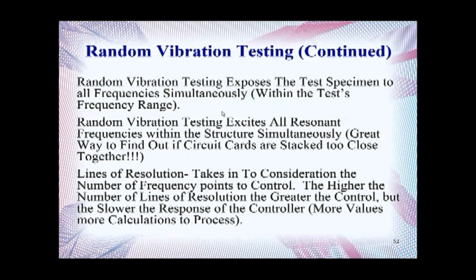Random Vibration Testing exposes the test specimen to all frequencies simultaneously within the test frequency range, and excites all resonant frequencies within the structure simultaneously. It's a great way to find out if circuit cards are stacked too close together, and it is an excellent way of finding all the failure modes for your test unit.